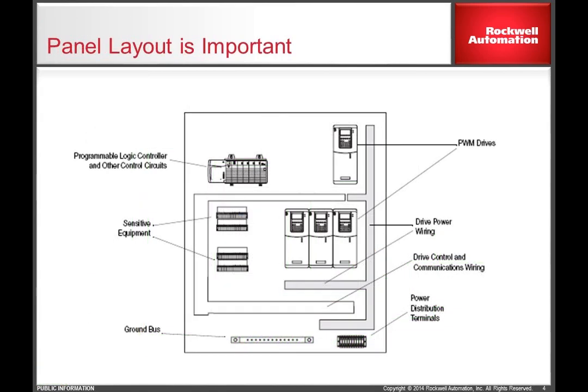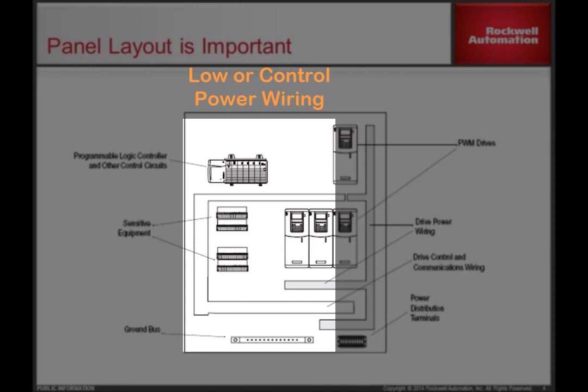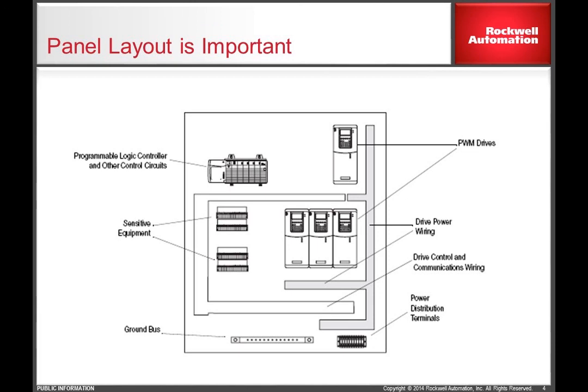Once the drive has been installed with all of the proper grounding considerations, proper panel layout needs to be considered. Always follow proper spacing requirements as stated in the installation or user manual to allow for proper airflow and cooling. A good layout plan starts by putting all the power input and output wire entry on the same side of the panel and placing sensitive equipment on the other side of the panel. The panel layout shown allows common mode noise current to flow away from sensitive electronic equipment and help prevent electromagnetic interference issues.